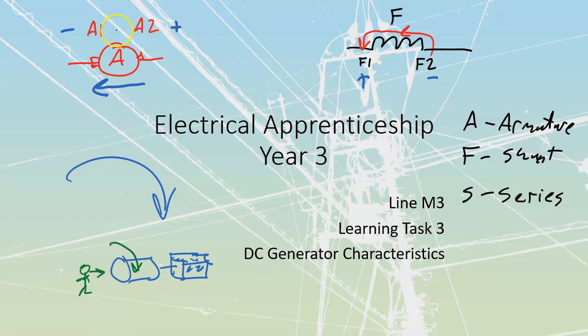That means that we are dealing with a clockwise rotation off of this. Then we are going to have A1 be negative. So don't worry too much about exactly what is going on for that direction of rotation. We've talked about direction of rotation. It's important. But for now, you just need to focus on these things here: my 1s are going to be my negative on my supply. My 2s are going to be my positive because we're flowing current through from 2 to 1 inside of here.